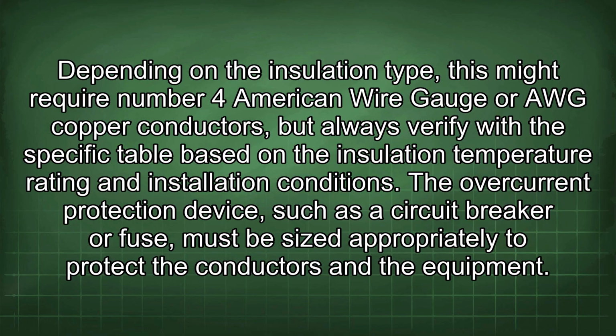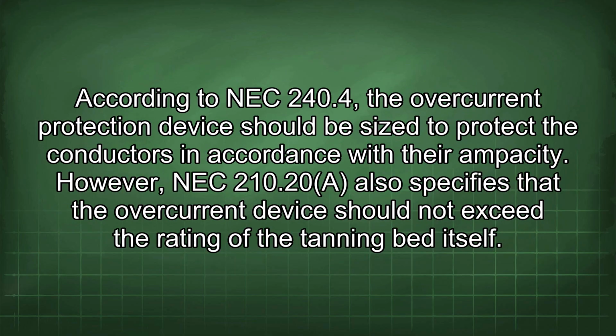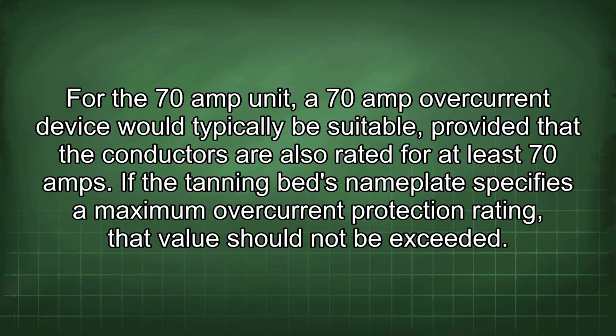The overcurrent protection device, such as a circuit breaker or fuse, must be sized appropriately to protect the conductors and the equipment. According to NEC 240.4, the overcurrent protection device should be sized to protect the conductors in accordance with their ampacity. However, NEC 210.20 also specifies that the overcurrent device should not exceed the rating of the tanning bed itself. For the 70 amp unit, a 70 amp overcurrent device would typically be suitable, provided that the conductors are also rated for at least 70 amps. If the tanning bed's nameplate specifies a maximum overcurrent protection rating, that value should not be exceeded.